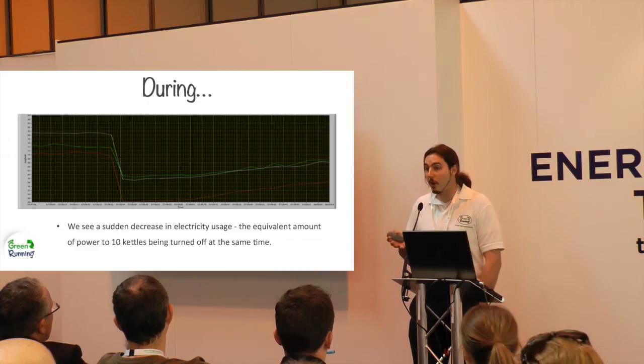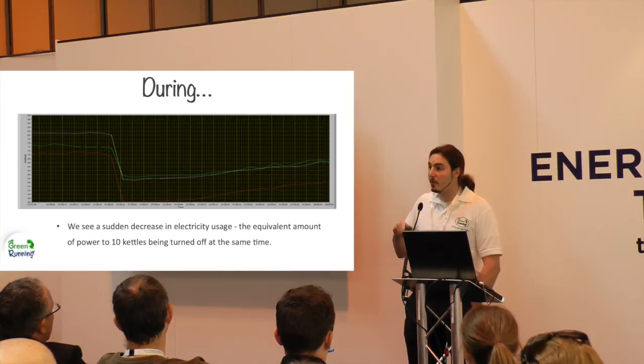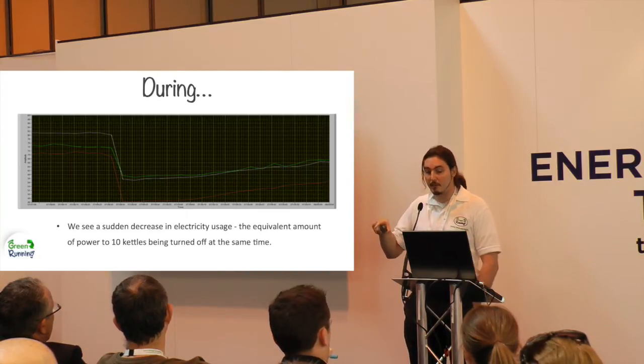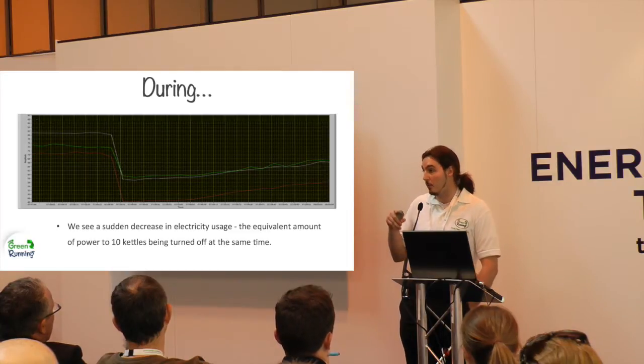So it's like, okay, well, that sounds like it could be playing with your power factor. Do you have anything that could be working on your power factor? And it turned out that the building, which they'd converted into offices, used to be an old machining plant. So in the building itself was a power factor correction unit, which nobody had been paying any attention to or worrying about.